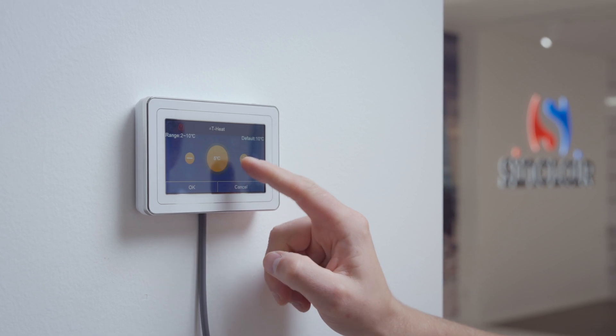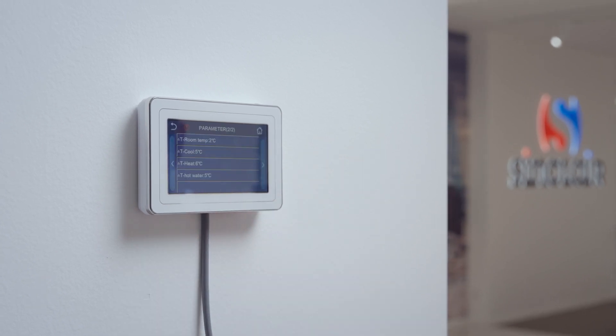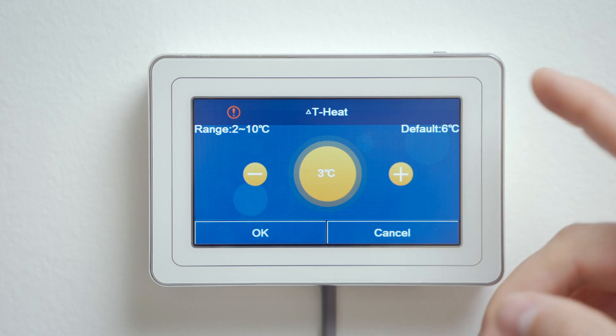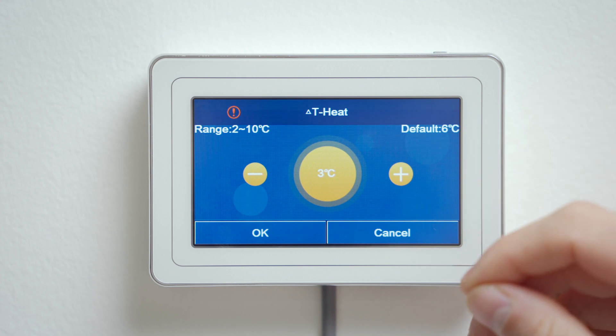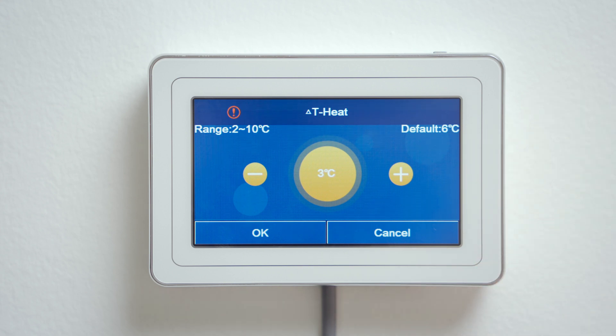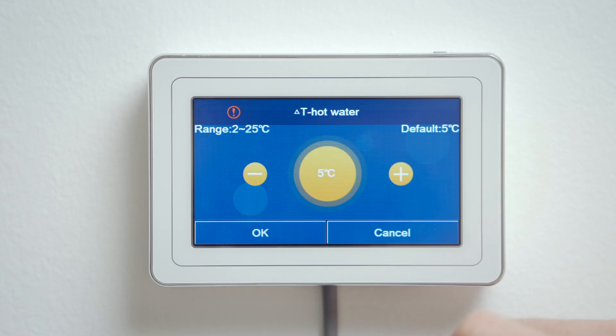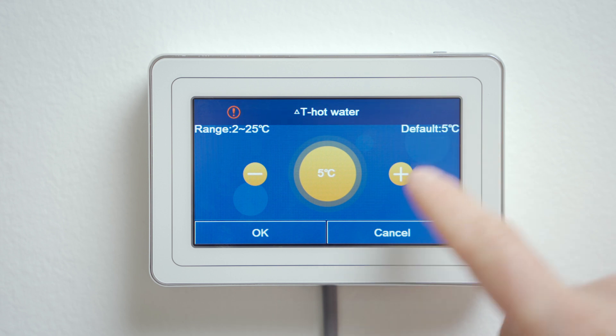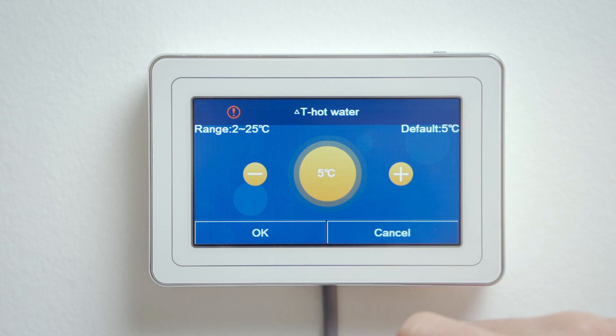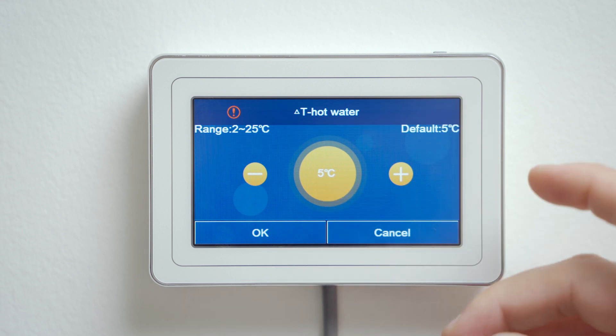A value of 5 to 6 degrees is suitable for radiators. For underfloor heating it's 2 to 3 degrees Celsius. On the next line, the domestic hot water hysteresis is set — here we recommend leaving the default setting of 5 degrees Celsius.